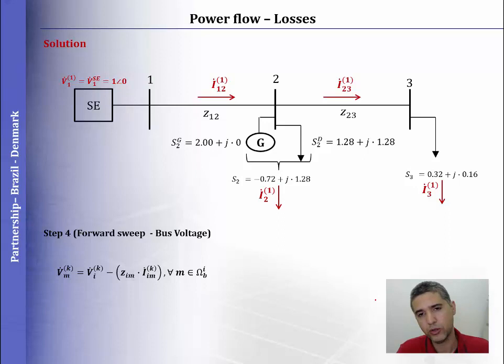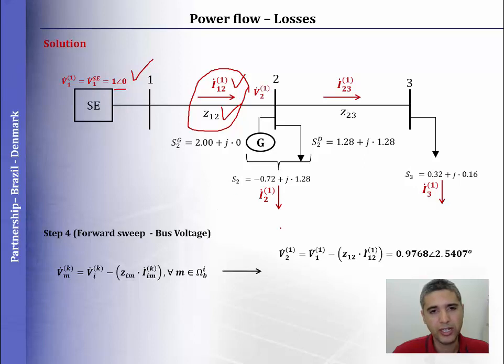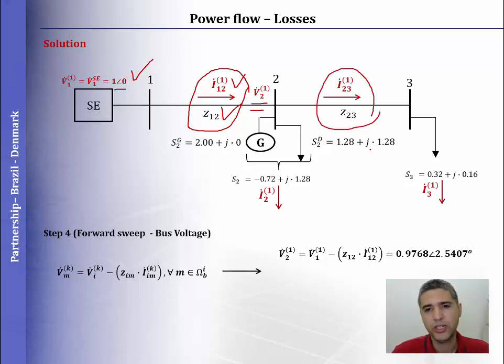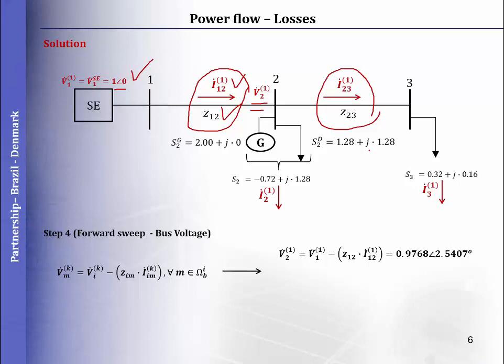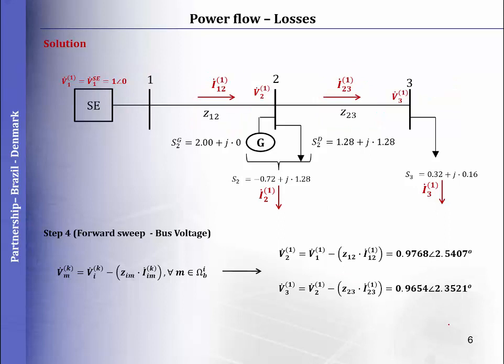Now we finish the backward sweep and start the forward sweep. We start at the substation, where the voltage is 1, and compute the voltage drop in the line by multiplying the current by the impedance. With the drop voltage in line 1-2, we compute the voltage at bus 2 for the first iteration. Then with the voltage at bus 2 and the drop voltage in line 2-3, we compute the voltage at bus 3.